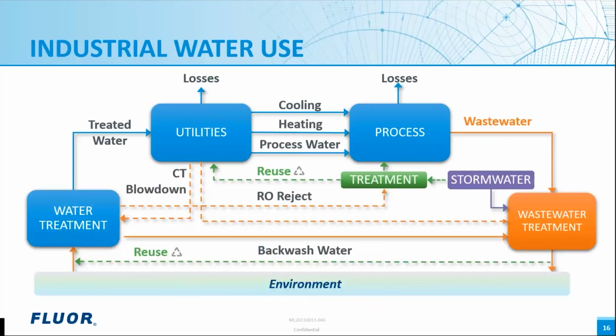In this diagram, you can see the fate of treated water as it passes through an industrial facility. Once the water is treated, it is passed through the utility system and eventually used in the plant process. Wastewater is therefore generated as it contacts the process and is sent to the wastewater treatment unit. When it comes to reuse, the cooling tower blowdown and the reverse osmosis reject, as shown in the orange dashed lines, are usually the place where water can be recovered. Other opportunities for reuse include the effluent from the wastewater treatment unit, which should be sent to the raw water treatment system for further processing before reuse.